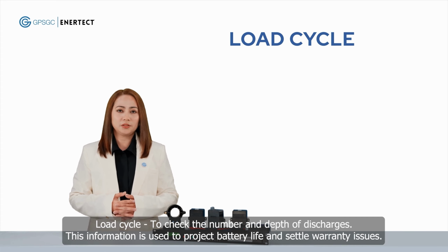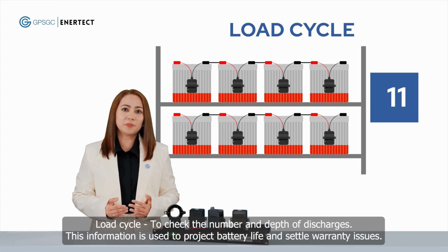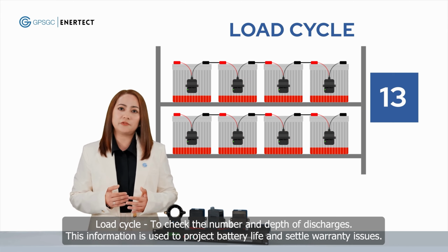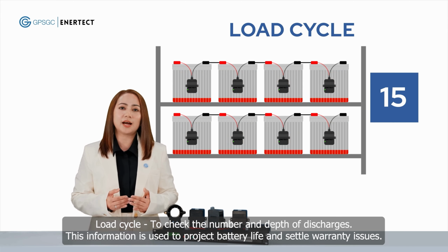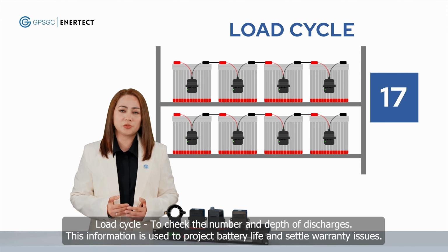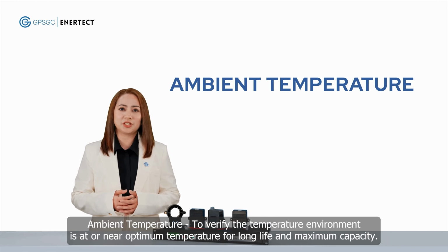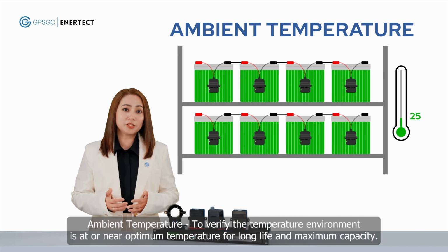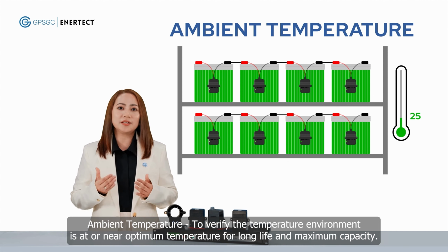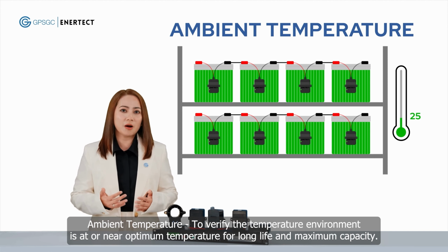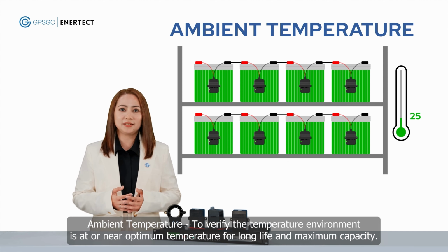Load cycle, to check the number and depth of discharges. This information is used to project battery life and settle warranty issues. Ambient temperature, to verify the temperature environment is at or near optimal temperature for long life and maximum capacity.